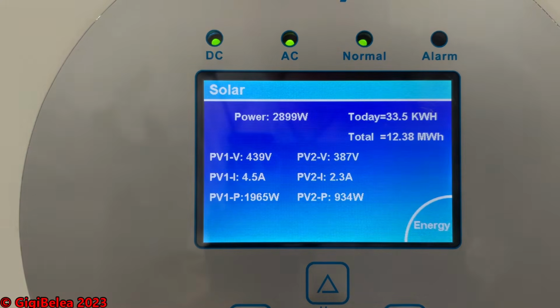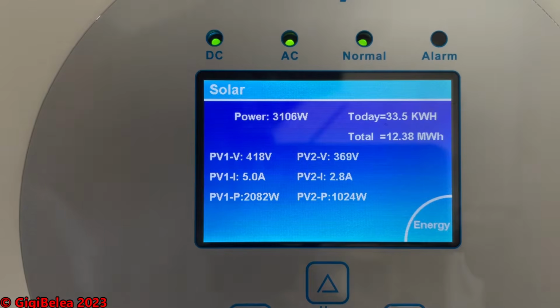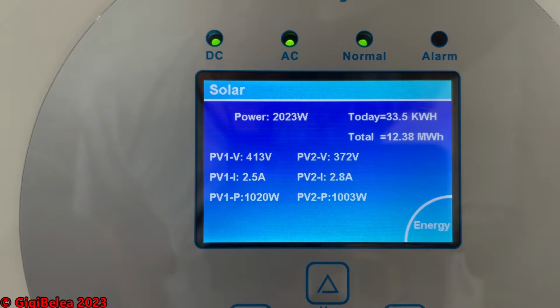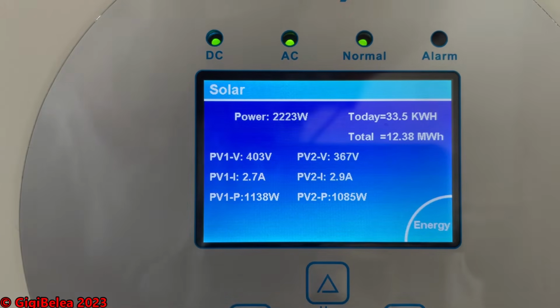As we can see, if I click on the panels, I can see exactly how much it's generating, and I'm going to disconnect one of the panels on the south, so the amperage should go to half. 4.9, we can see it's 5 amps. And let's try to disconnect the other panel, the other string on the south. Disconnected, amperage going to half, same voltage, and you can see that it's reflected in the voltage and in wattage.